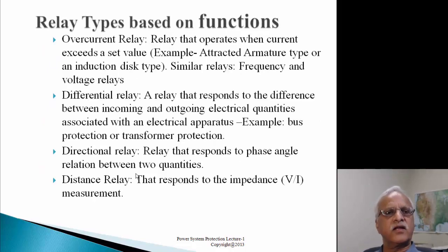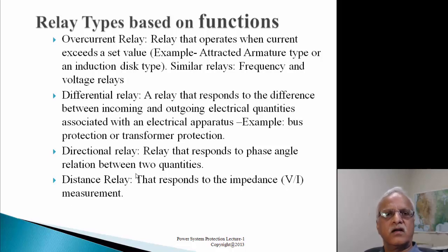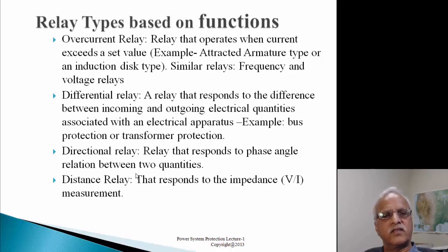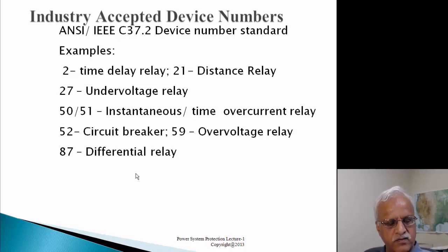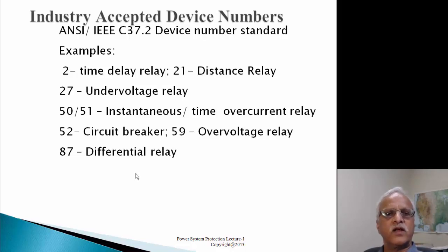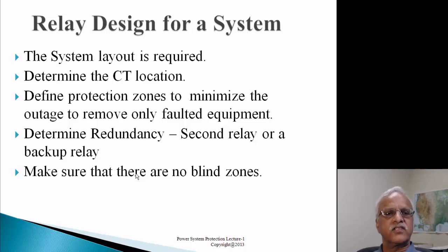Based on functions, we have overcurrent relays, differential relays that compare current into and out of equipment, directional relays, and distance relays. In the industry, relay functions have IEEE numbers defined in C37.2: 2 is the time delay relay, 21 is the distance relay, 27 is under-voltage relay, and 50/51 is instantaneous/time overcurrent. You can look at the C37.2 standard for a full list.